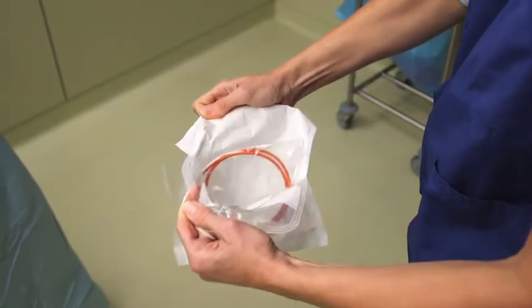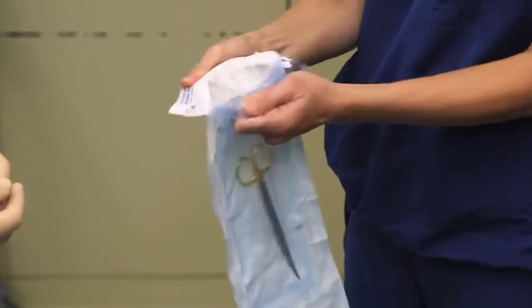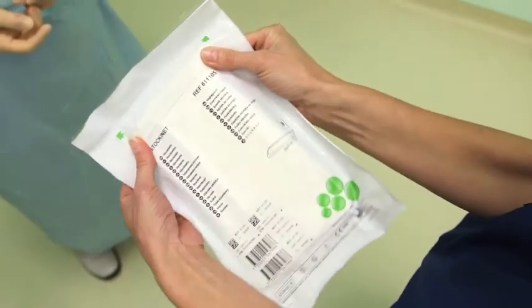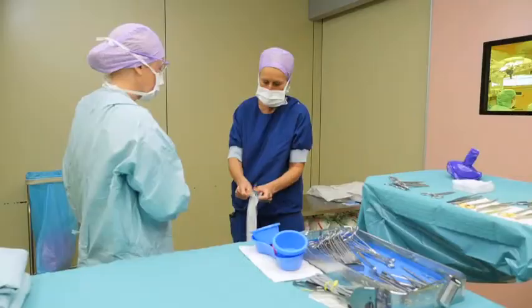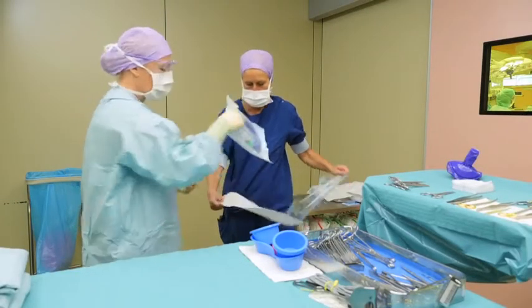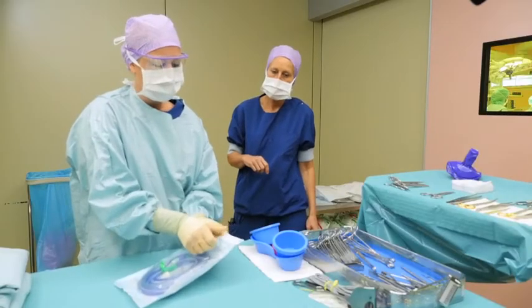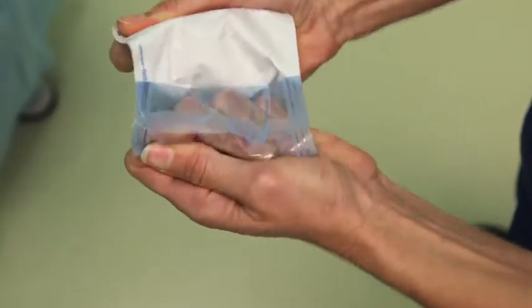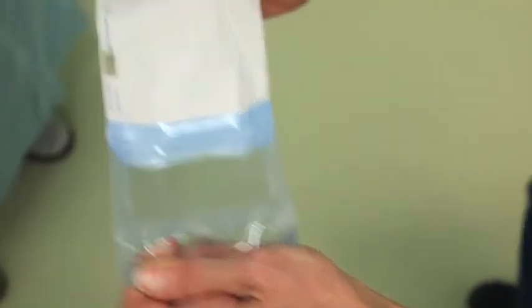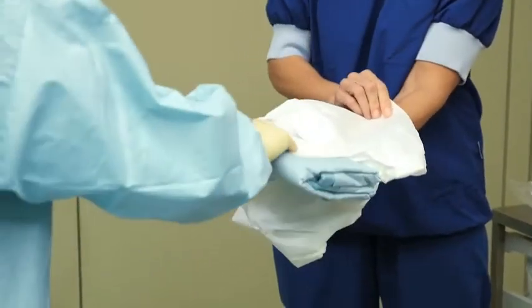The seals of the packs should be peeled slowly and evenly starting at the specified position depending on the design of the sterile barrier system. This is usually at the chevron end or may be indicated with arrows. For large packs, the best approach is often to start peeling first on both edges so that the last peeling is the middle of the seal. You should respect the direction of peel indicated by a peel symbol. Minimize the creation of fibers and particles without tearing or delamination. Bursting or tearing the barrier system will result in a high risk of contamination. Peel the flap completely and fold it backwards. Maintain the position of the product to avoid contact with unsterile areas of the barrier system including the seal area. Arms and body should not enter the area above the barrier system, and an opening should be created large enough to allow the product to be removed without touching unsterile areas.